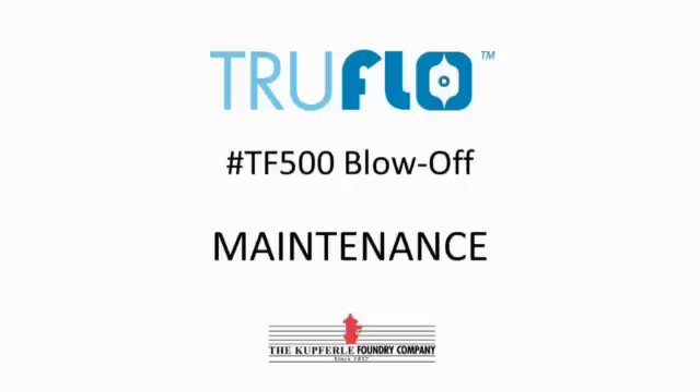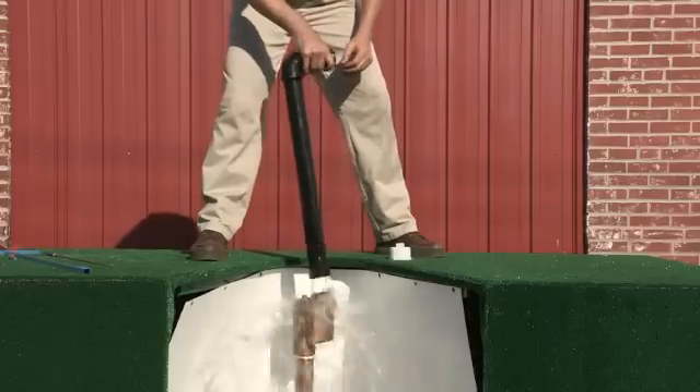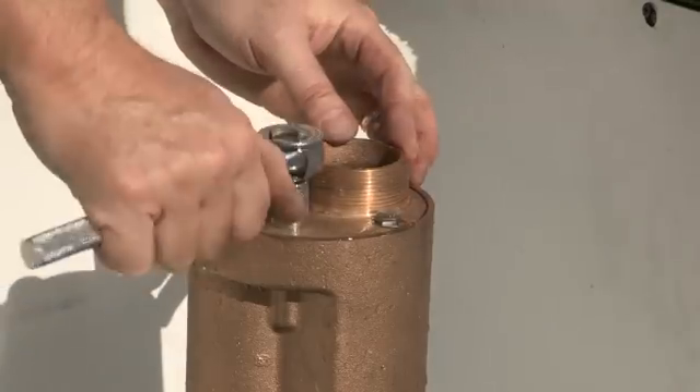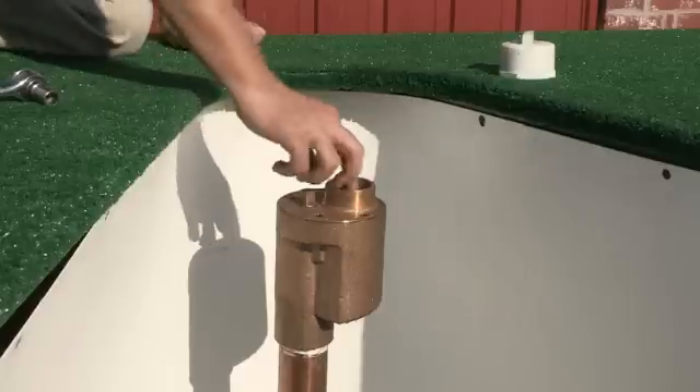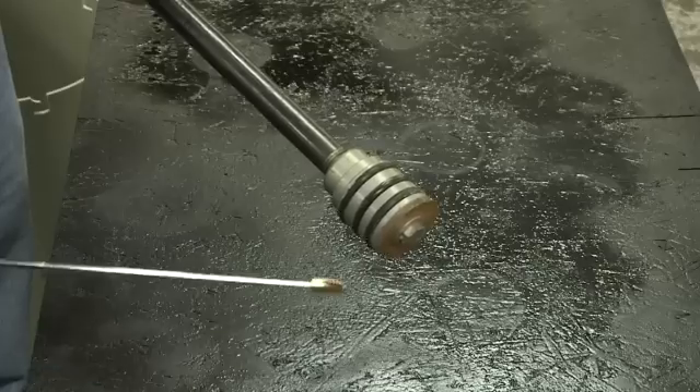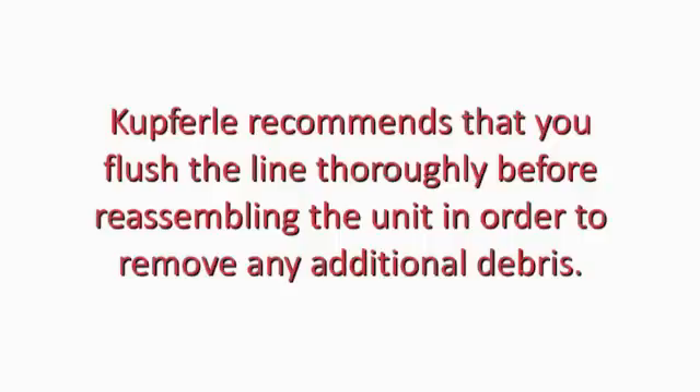To do maintenance on the TF500, turn the water off to isolate the unit. Remove the four top cap bolts, then lift the entire working part assembly out of the unit and inspect the O-rings and seat for wear. Kupferle recommends that you flush the line thoroughly before reassembling the unit in order to remove any additional debris.